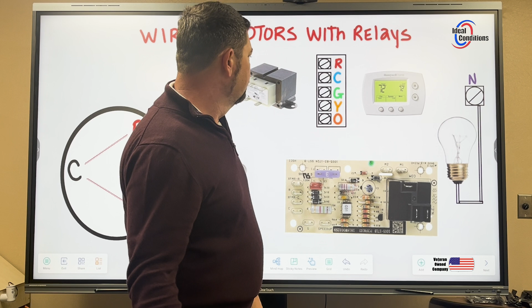When we talk about wiring these components up, we talk about safety. Your safety is paramount, and the well-being of the equipment as well. We want to make sure it's just as reliable when you're done as it needs to be, and that you create no additional work because something wasn't wired properly. The best way to practice this is not wiring one component at a time, but wiring one leg of power at a time. We're going to start with L2 since it's the closest to my transformer.